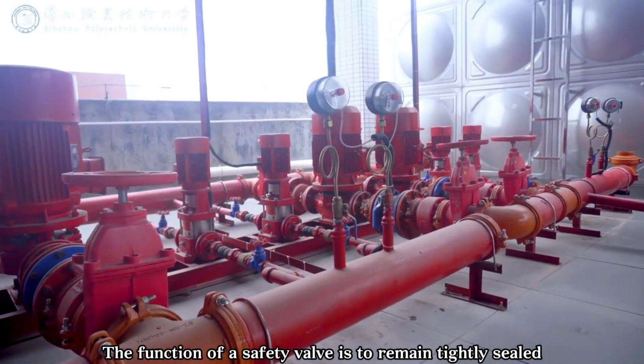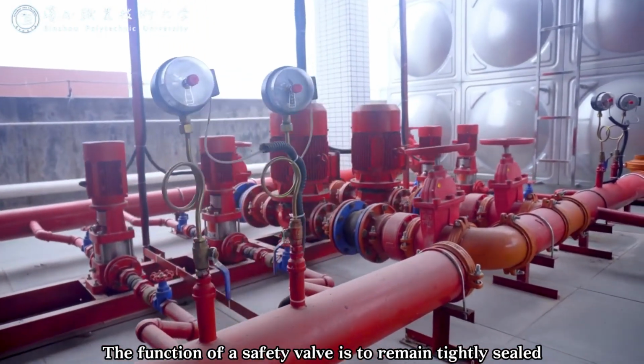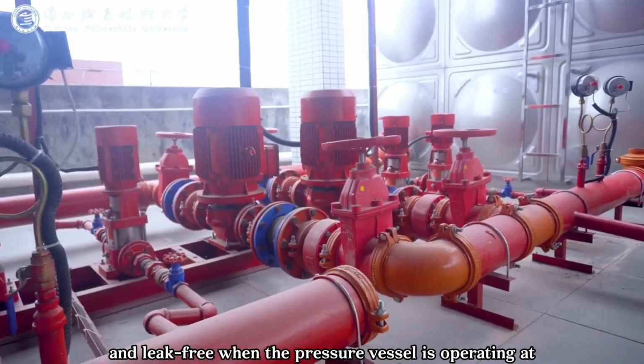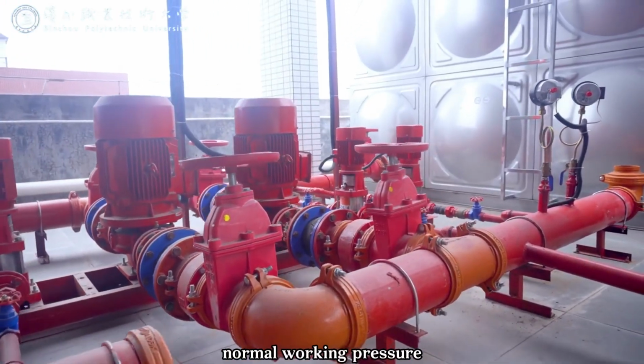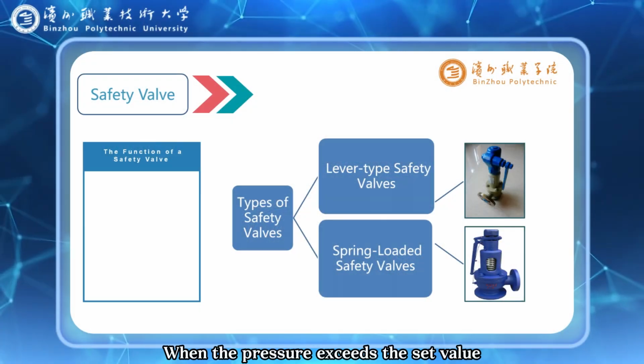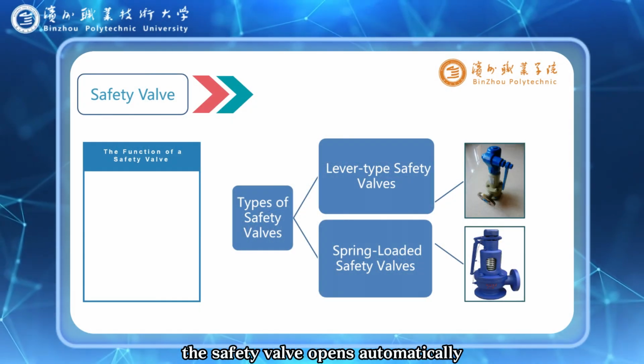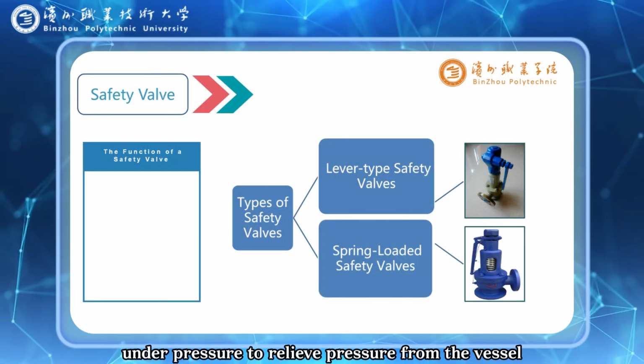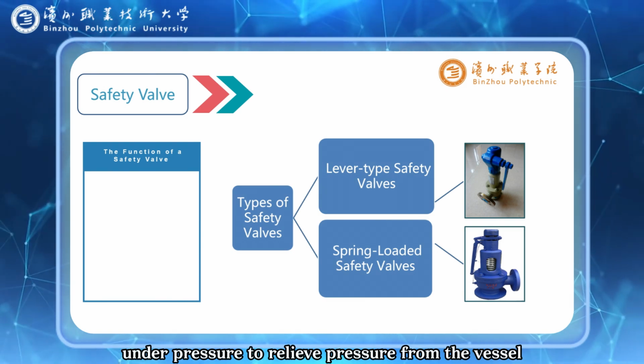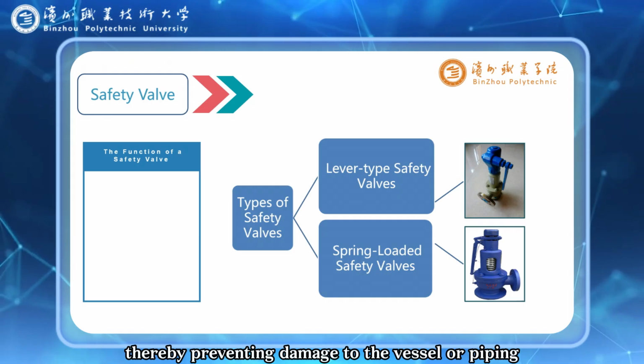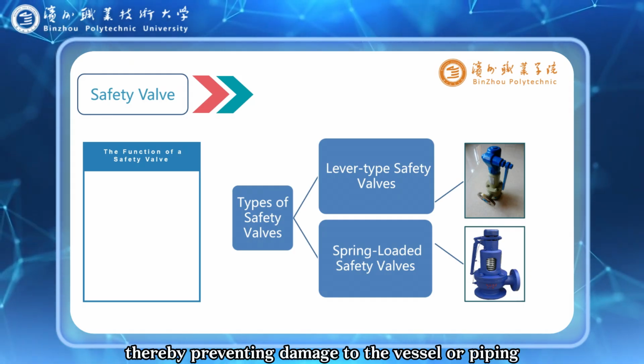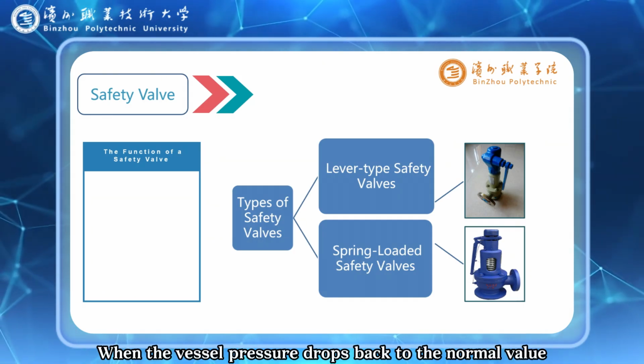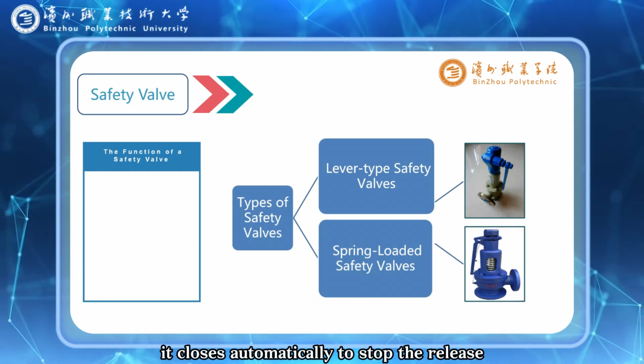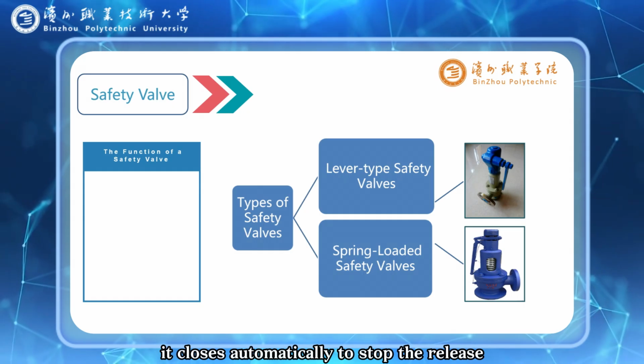The function of a safety valve is to remain tightly sealed and leak-free when the pressure vessel is operating at normal working pressure. When the pressure exceeds the set value, the safety valve opens automatically under pressure to relieve pressure from the vessel, thereby preventing damage to the vessel or piping. When the vessel pressure drops back to the normal value, it closes automatically to stop the release.